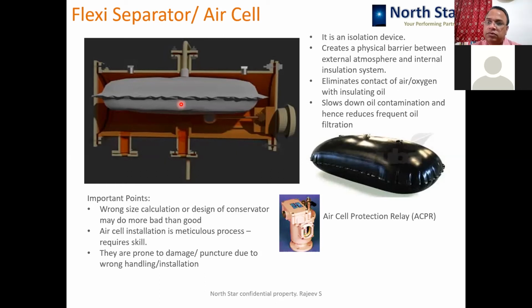In order to detect an air cell defect or puncture, air cell protection relays are now available, which you can put on your conservator, and you will get a signal when the air cell has stopped functioning or has developed a leak. So this device will tell you that your air cell is not working. So you can use this small device.